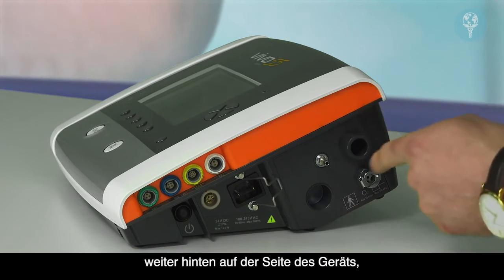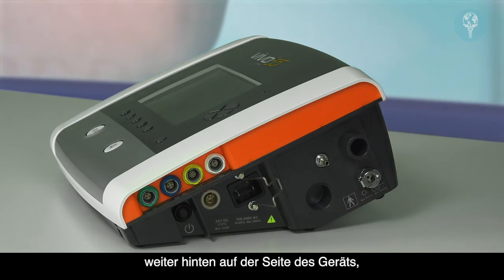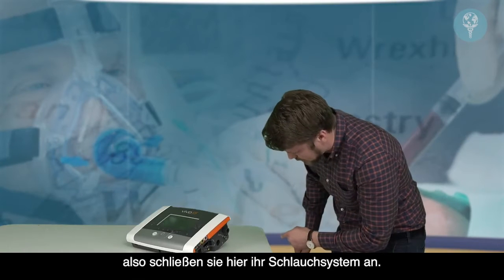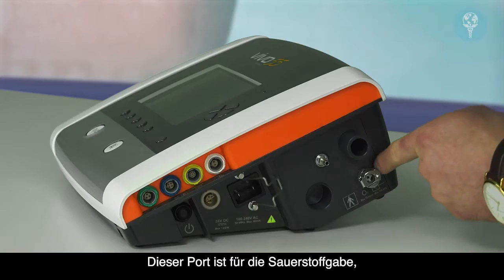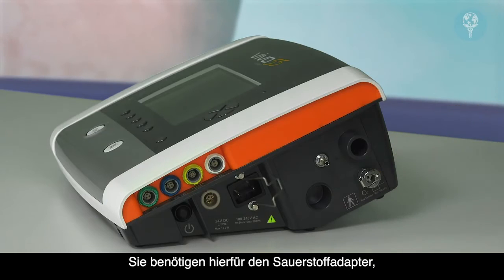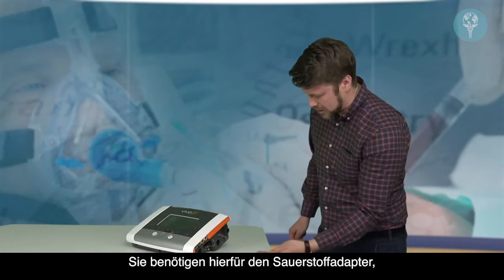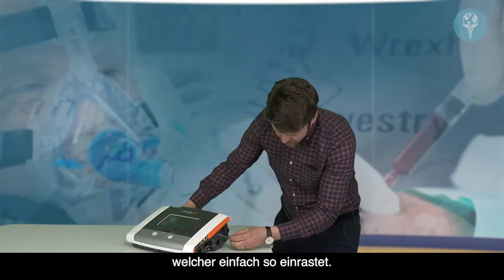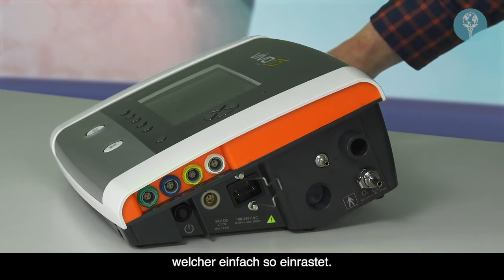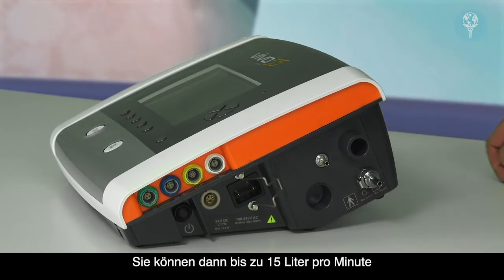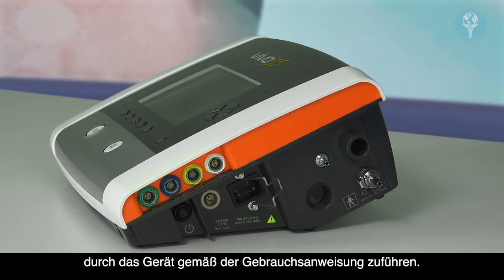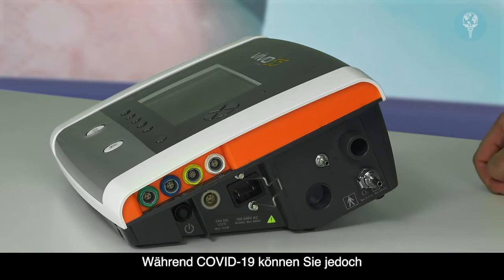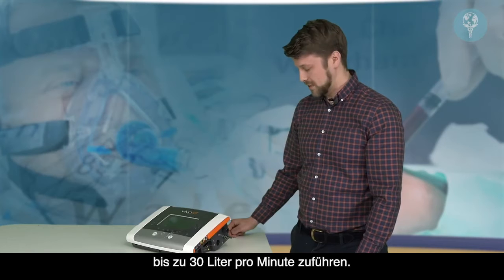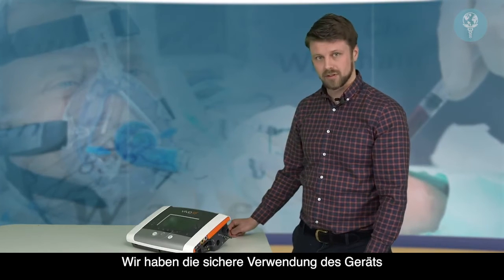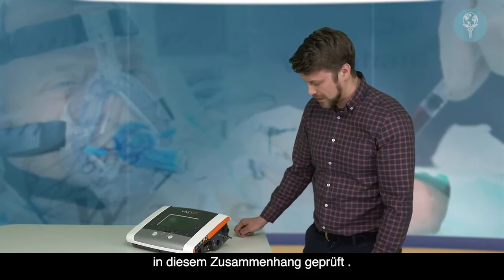Your main air outlet is on the rear of the device. Okay, so you attach your breathing circuit here, and this port is for your oxygen entrainment. So you would need the oxygen adapter, which just clicks into place like so, and then you can put up to 15 litres per minute through the device as per the instructions for use, but during COVID-19 you can go up to 30 litres per minute. We have verified the device as safe to use in that manner at this time.